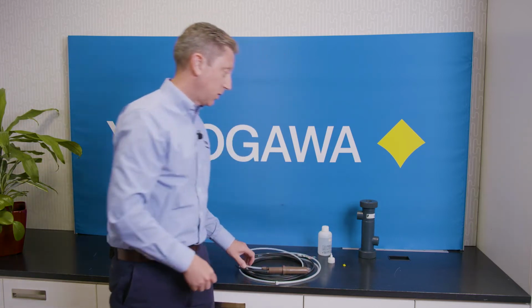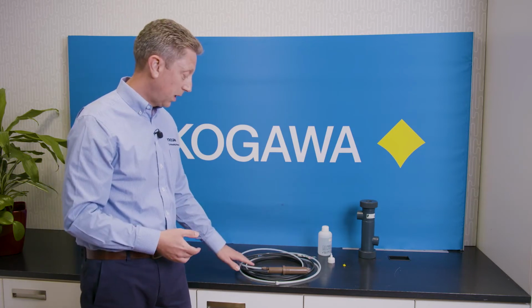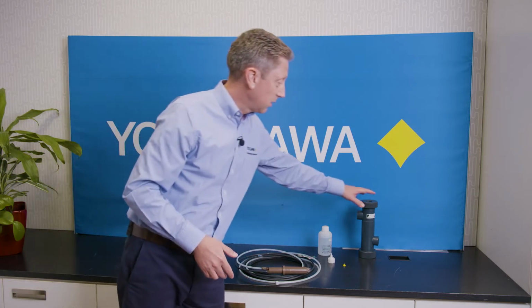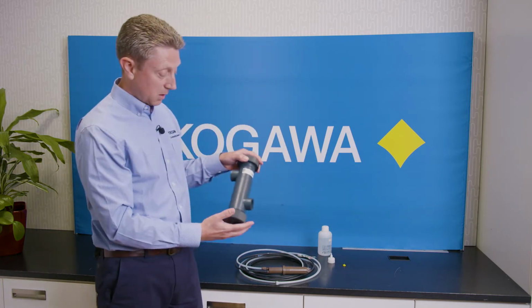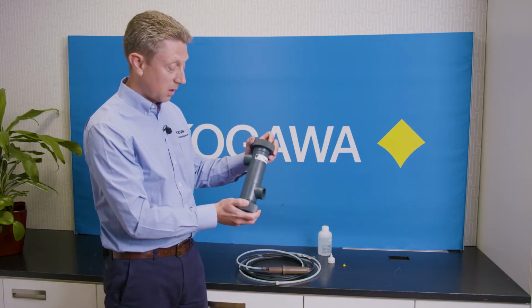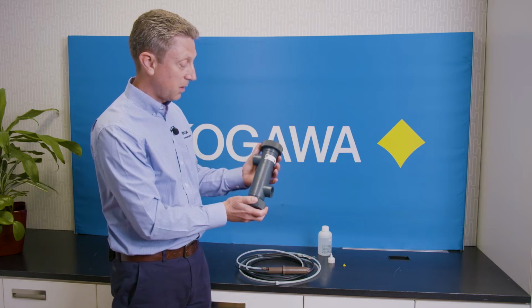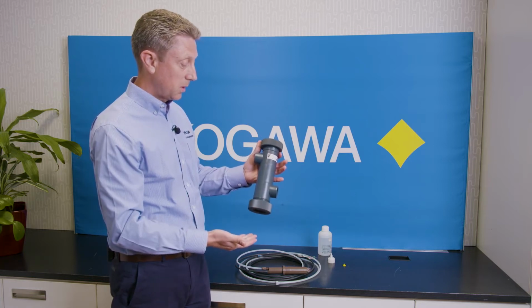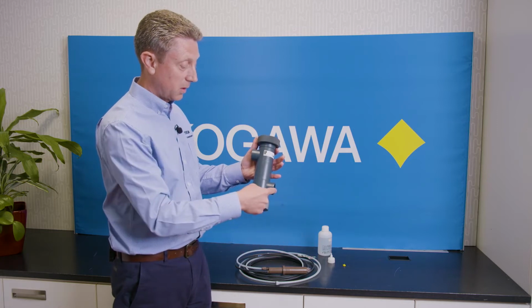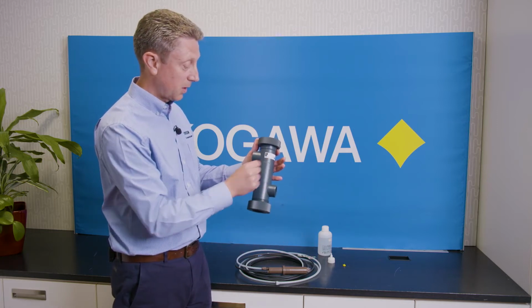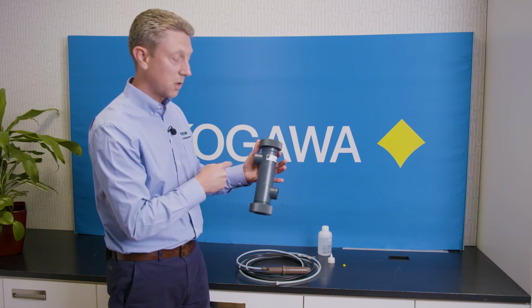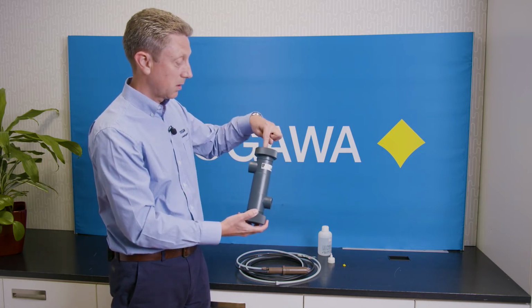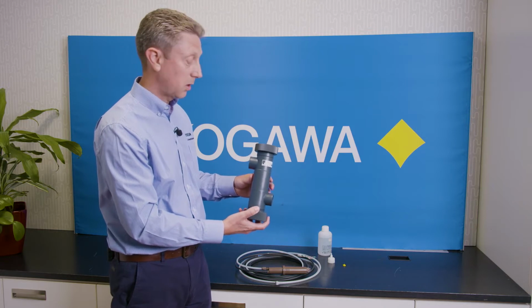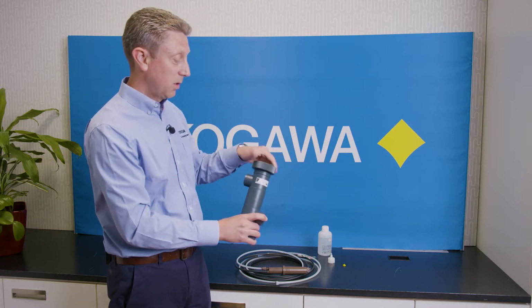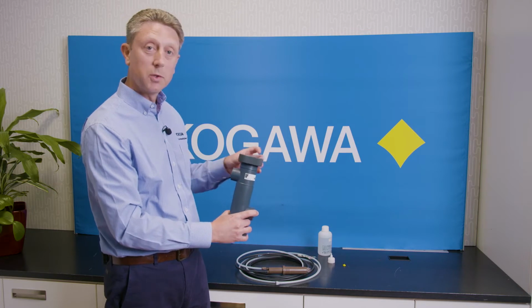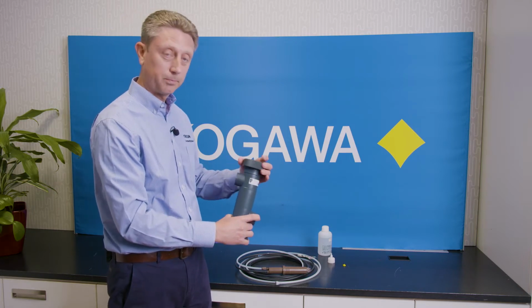Now the very next step should be to position or prepare your sensor for installation, and for that you need to put it into some kind of fitting. This particular fitting I have here is a flow-through fitting, our PH8 HF, and what this is designed to do, our sample would flow into this connection at the bottom, up through the fitting and out of this connection at the side. Meanwhile our pH sensor comes and is positioned in through the top here. So we'll have to remove this cap and thread the cable and the hose through here, ready for installation.